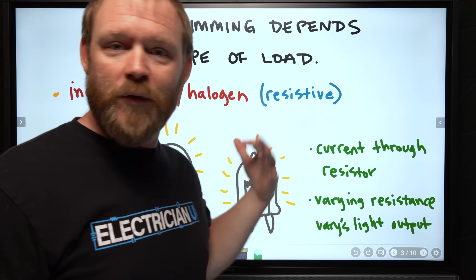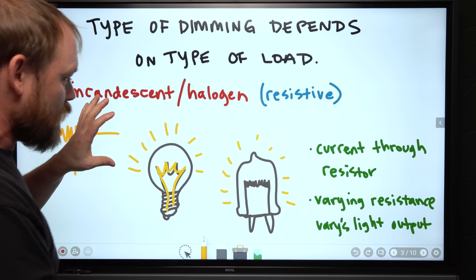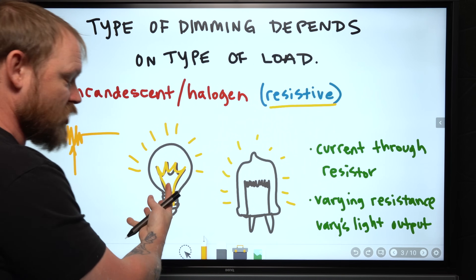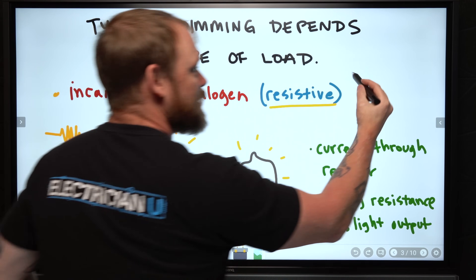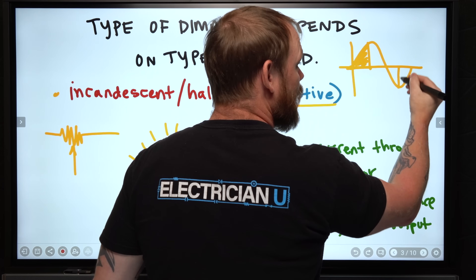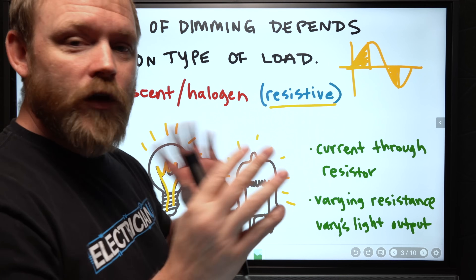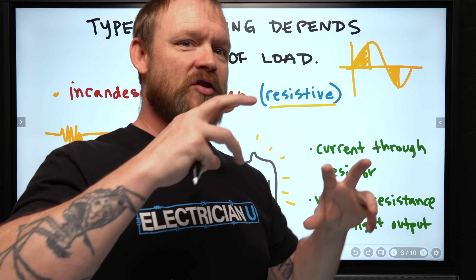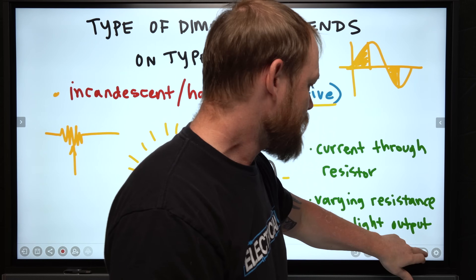The problem is that resistive dimming doesn't work with everything - it doesn't work with LED, HID, or ballasted lighting. For purely resistive light, we just vary the resistance. But we can also electronically control this using phase cutting, where we take a sine wave and cut half of it out - cutting the leading edge and only using the reverse part. If we're cutting a portion of the phase, less power gets delivered to the load. That's why LEDs have forward phase and reverse phase.